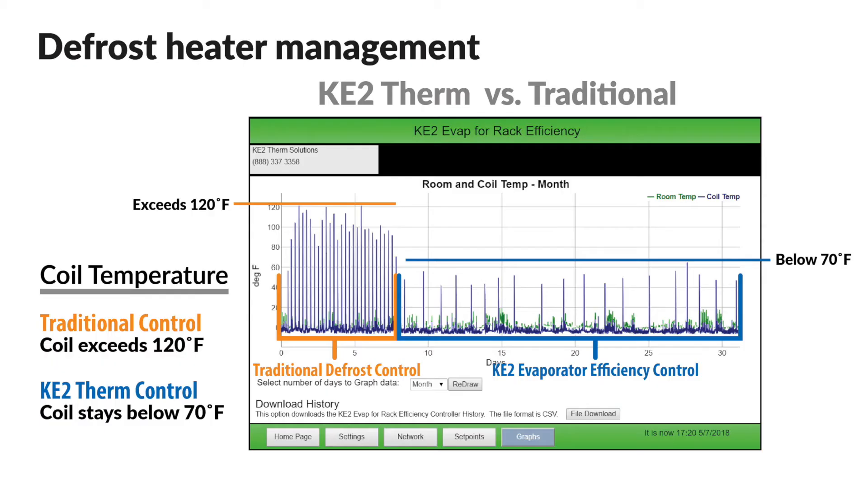Another food-saving benefit of the KE2 Evap's defrost heater management is the reduction in temperature spikes. Most refrigeration controllers activate the defrost heaters, but then they don't control the temperature. This causes larger than necessary spikes in the walk-in temperature during every defrost cycle.